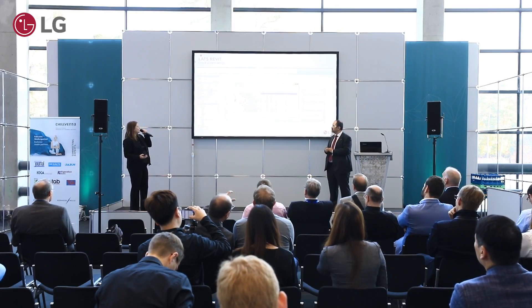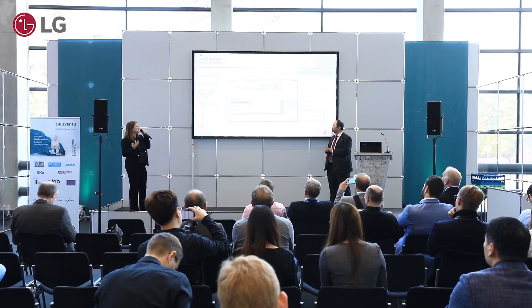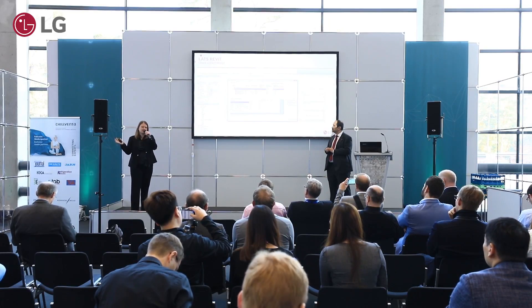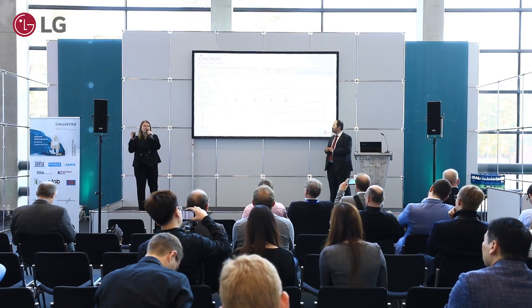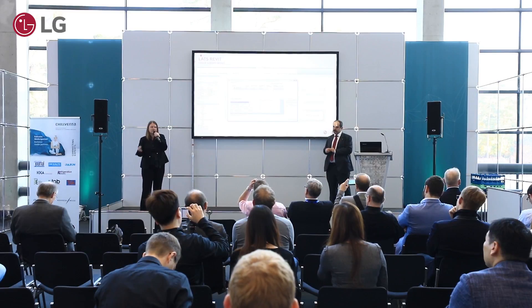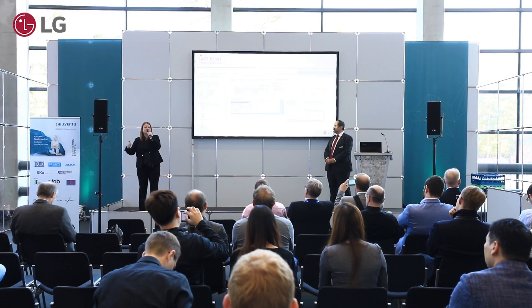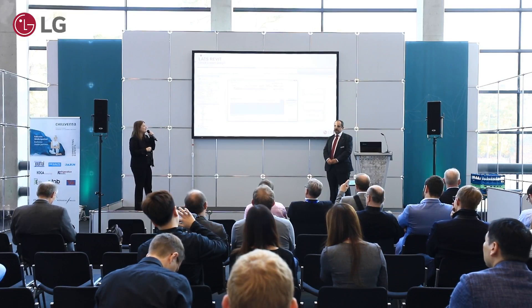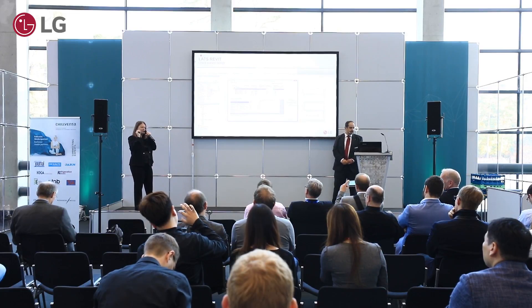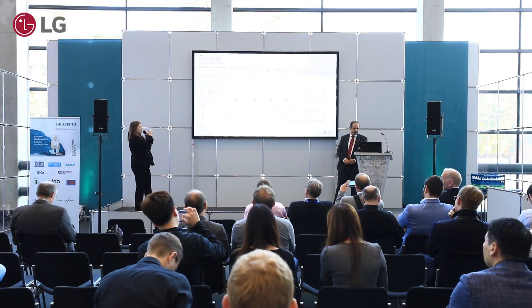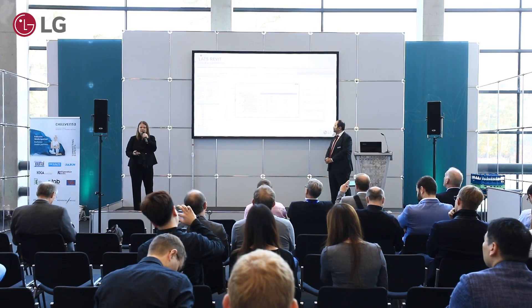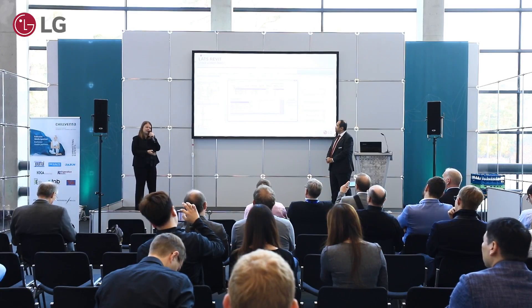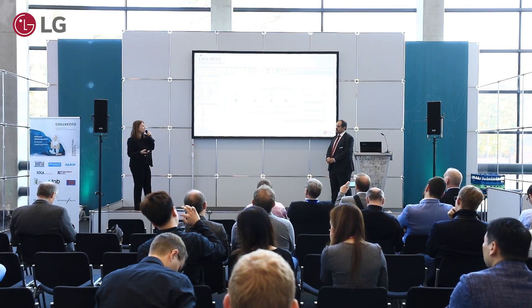At the same time, you will have the possibility of running a simulation. After you have completed your selection of indoor units and chosen your preferred outdoor units — for example, a side-discharge outdoor unit where the airflow blows to the side, or a top-discharge unit — you have various selections from our VRF outdoor unit range. After the selection is done, by a simple click of a button, you will have a simulation that tells you how much capacity you can provide to your building, and also how much additional refrigerant needs to be added when commissioning or installing the system.